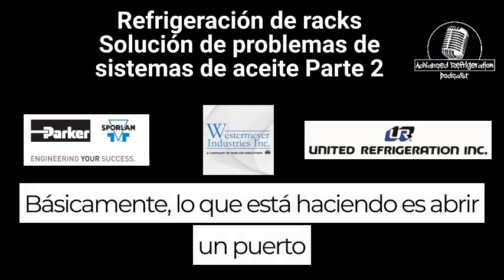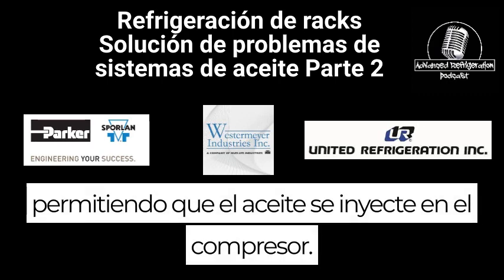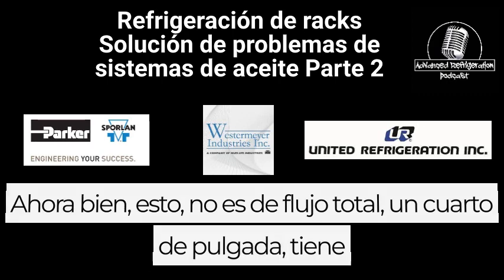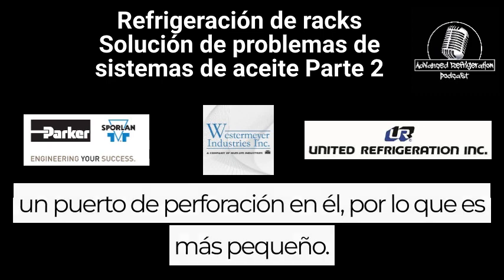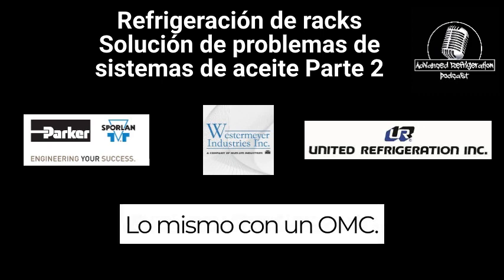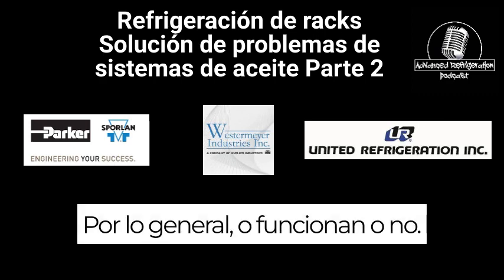Basically what it's doing is opening a ported solenoid valve inside of the oil float that allows oil to inject into the compressor. Now, it's not full flow quarter inch. It has a drill port in it, so it's smaller. Same thing with an OMC. It's the exact same, except it's using 120 or 208. Usually they either work or they don't.